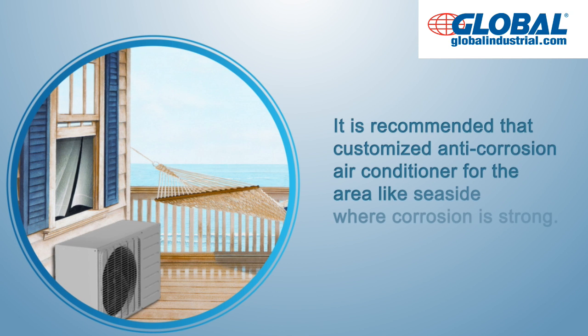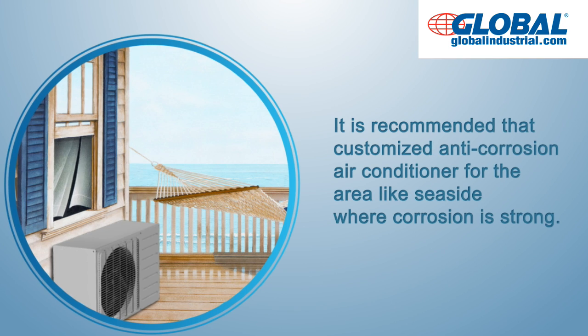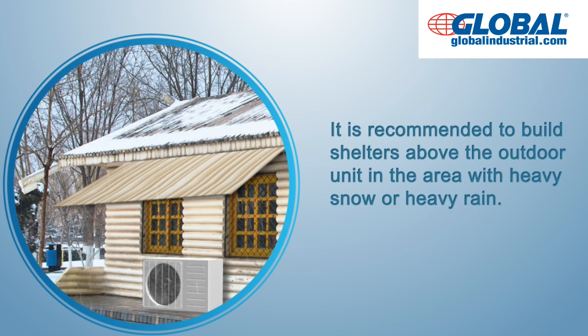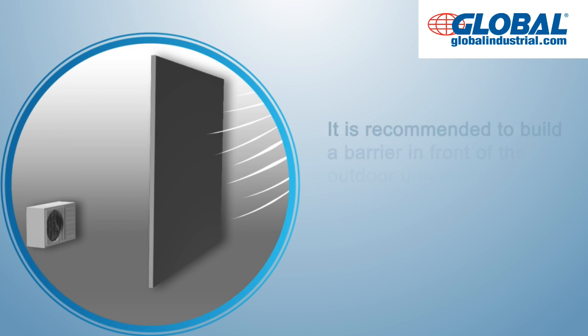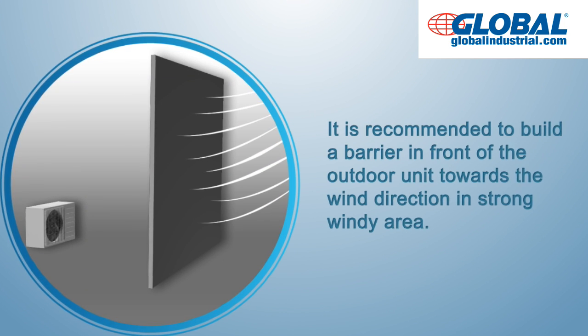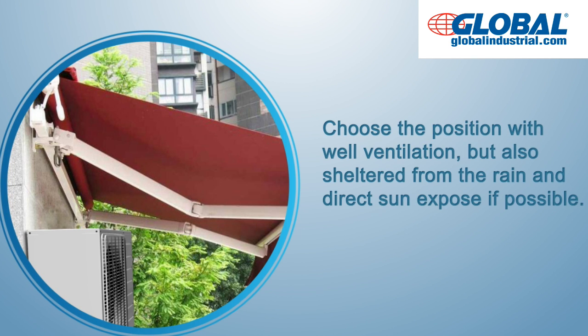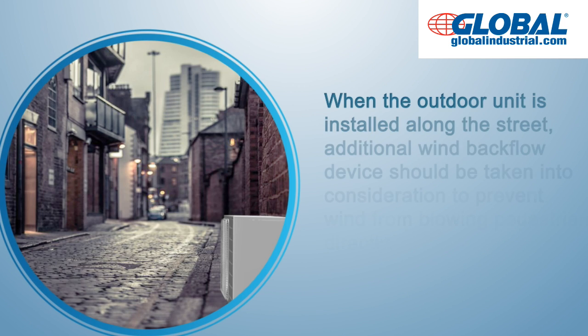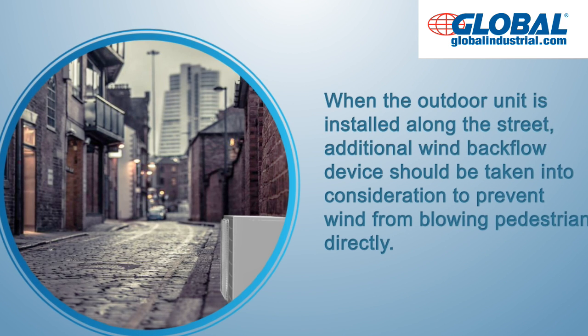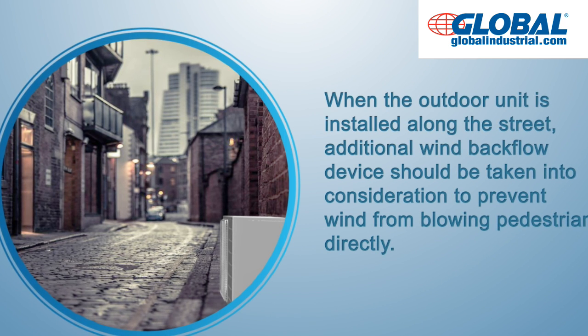It is recommended to use a customized anti-corrosion air conditioner for areas like seaside where corrosion is strong. It is recommended to build shelters above the outdoor unit in areas with heavy snow or heavy rain. It is recommended to build a barrier in front of the outdoor unit towards the wind direction in strong windy areas. Choose a position with well ventilation but also sheltered from rain and direct sun exposure if possible. When the outdoor unit is installed along the street, an additional wind backflow device should be taken into consideration to prevent wind from blowing pedestrians directly.